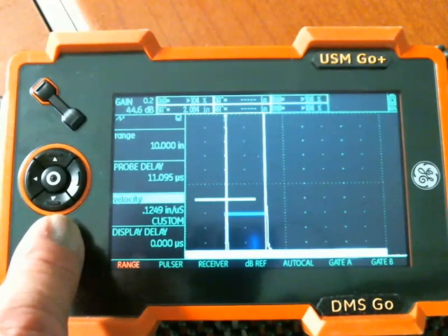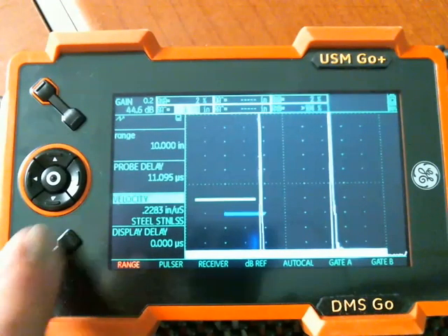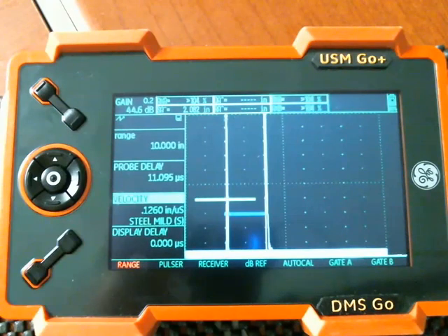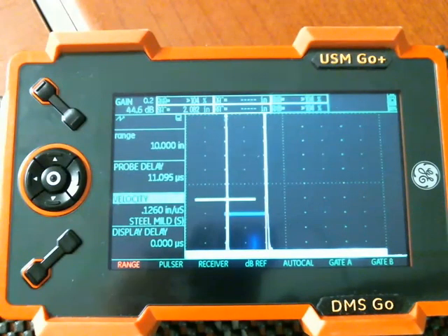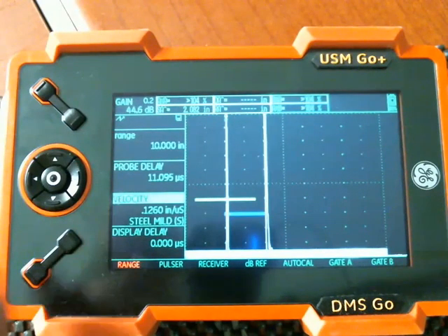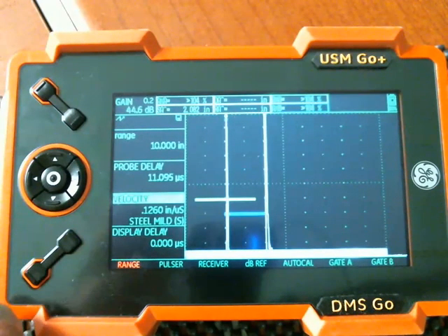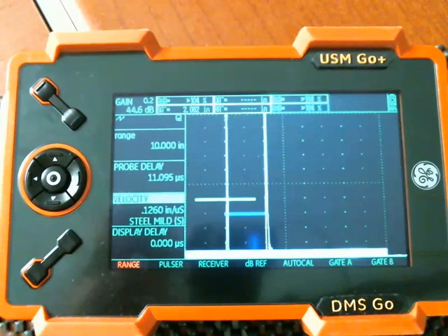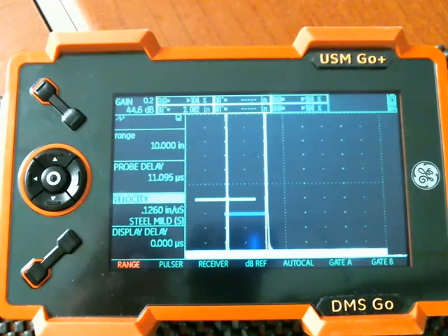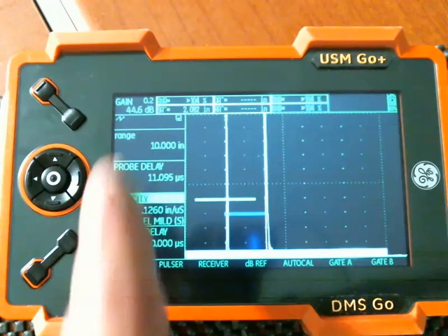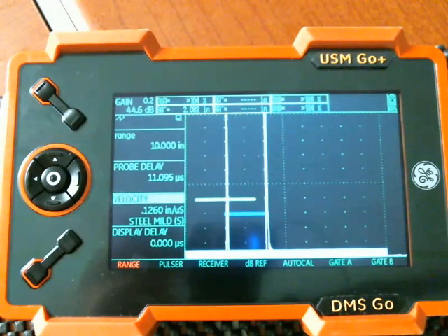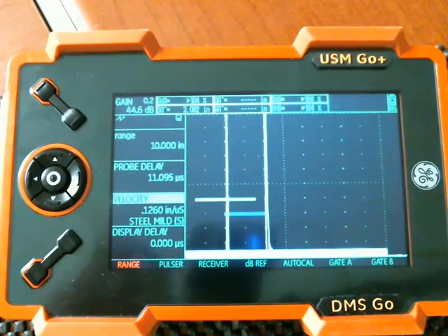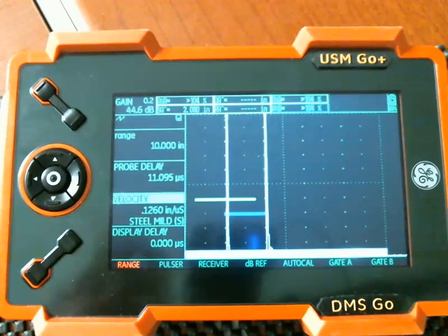I've already done a calibration here, but we're going to clear that. We're going to go to mild steel, shear. Since we're using an angle beam probe, we want shear velocity. This just gets us a good starting point. I've selected a range that gives me plenty of room to see the signals from the two inch and four inch radii on the IIW block.